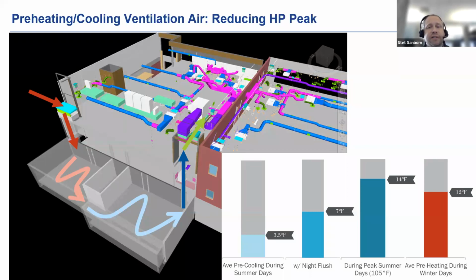And so we were able to see significant temperature peak reductions, both in the wintertime, when that thermal labyrinth warmed up the air by the time it gets to the heat pump or the VRF head units, and in the summertime, when we were able to reduce that summer peak as well. That thermal labyrinth, or preheating, pre-cooling strategy, was a really effective way for us to downsize the heat pump and reduce the impact on the electrical service, et cetera.